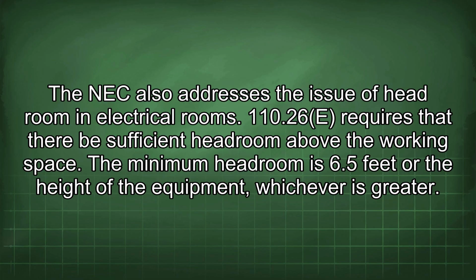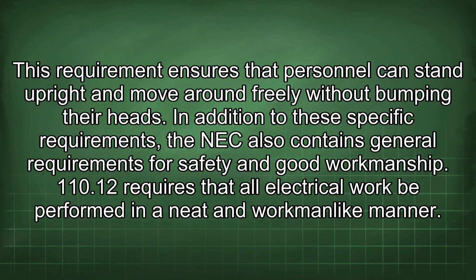The NEC also addresses the issue of headroom in electrical rooms. 110.26(E) requires that there be sufficient headroom above the working space. The minimum headroom is 6.5 feet or the height of the equipment, whichever is greater. This requirement ensures that personnel can stand upright and move around freely without bumping their heads.